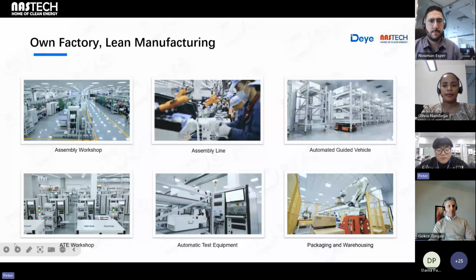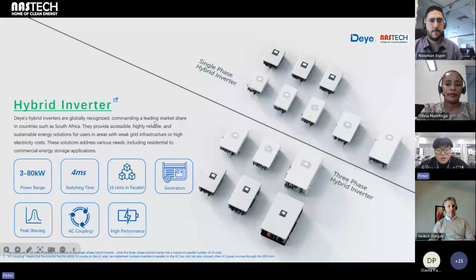And first, our hybrid inverter, which is also the main product in the inverter products. Now the power range is from 3 to 80 kilowatt. And the switching time for the single phase hybrid inverter is only 4 milliseconds. It's the fastest speed in the industry. And it can easily support all your UPS needs. You can use your load even when the grid blacks out, and it can still be powered without any gap. And the three-phase hybrid inverter is 10 milliseconds, but it's also good enough to do the UPS function.